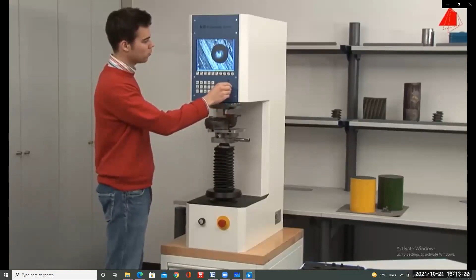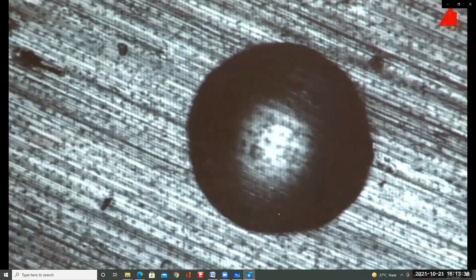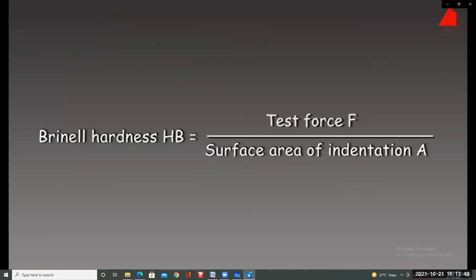With the control knob, the tester places 4 measuring lines on the edges of the indentation to measure its diameter. That's it. The testing machine can now calculate the Brinell hardness. The hardness value is defined as test force F in the old unit kilopond, divided by the area of the indentation A in square millimeters. The result is displayed on the bottom left-hand corner of the screen and amounts to 250.